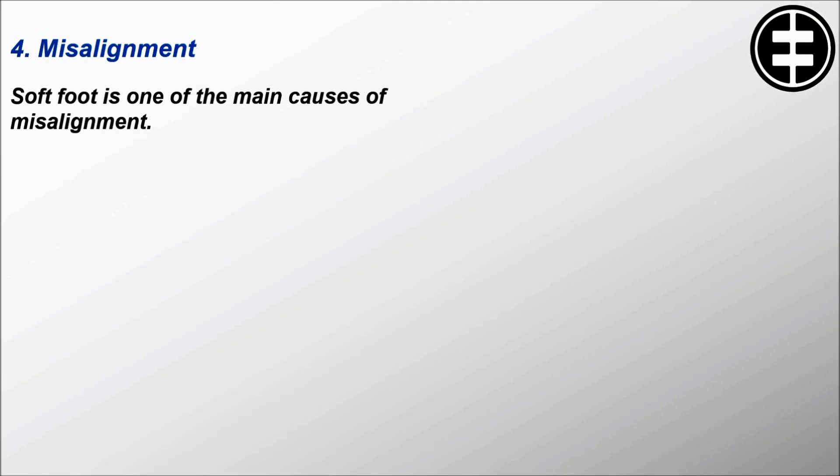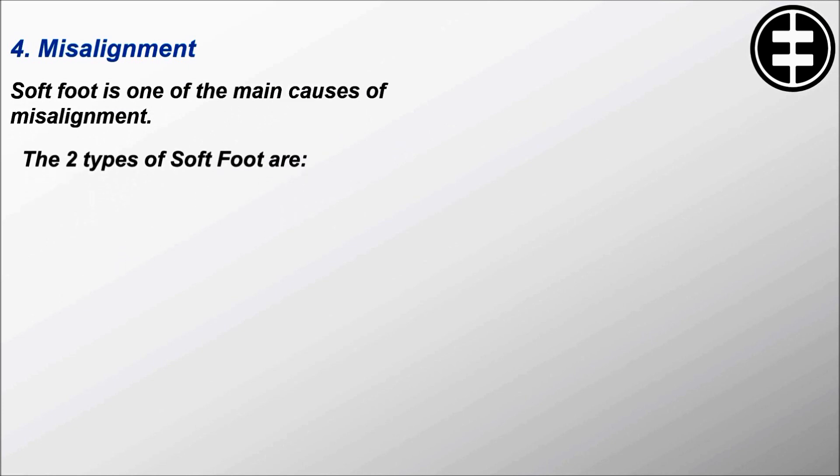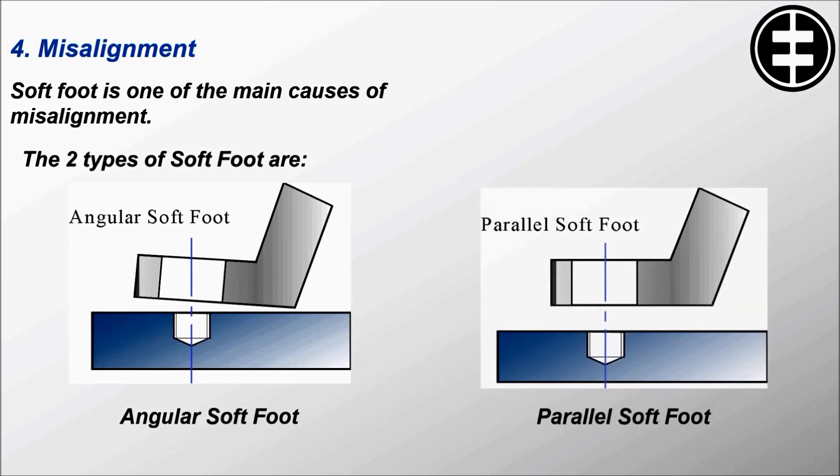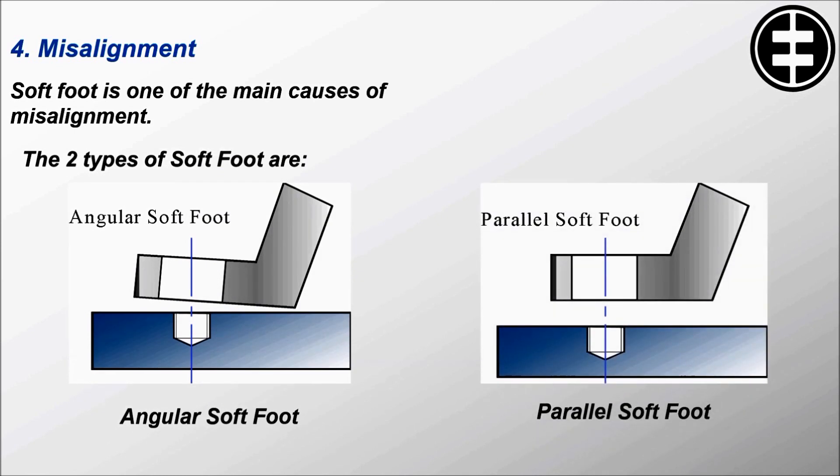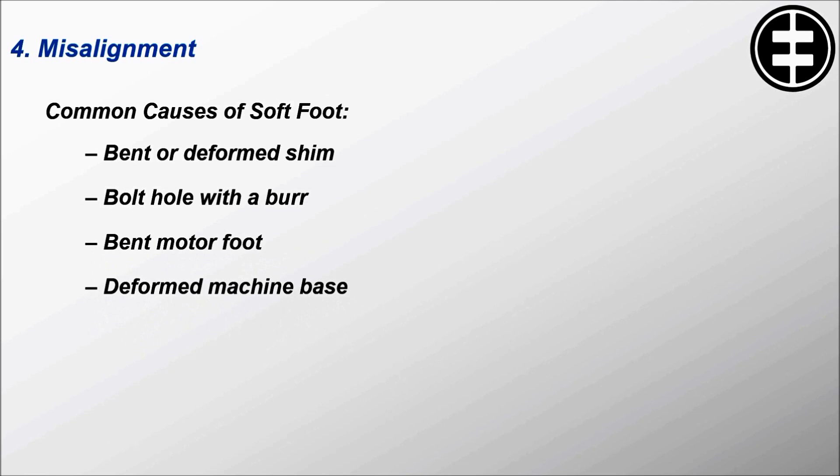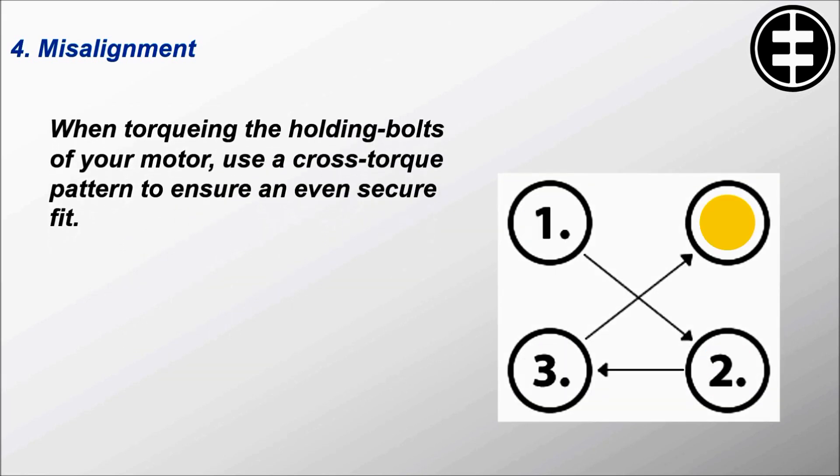Soft foot is one of the main causes of misalignment. The two types of soft foot are angular soft foot and parallel soft foot. Common causes of soft foot: bent or deformed shim, bolt hole with a burr, bent motor foot, deformed machine base. When torquing the holding bolts of your motor, use a cross torque pattern to ensure an even, secure fit.